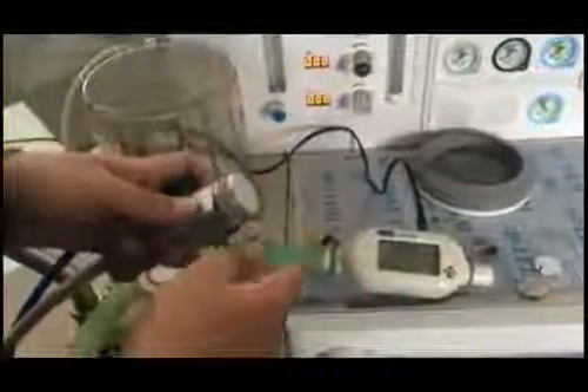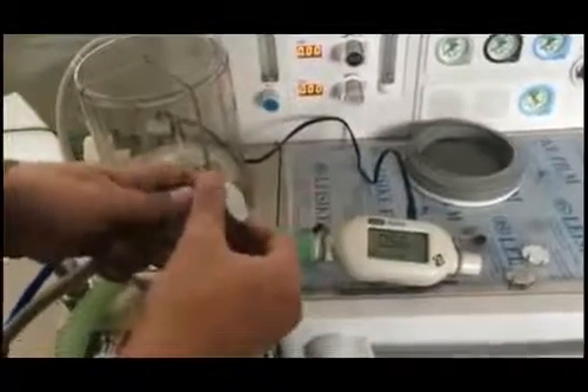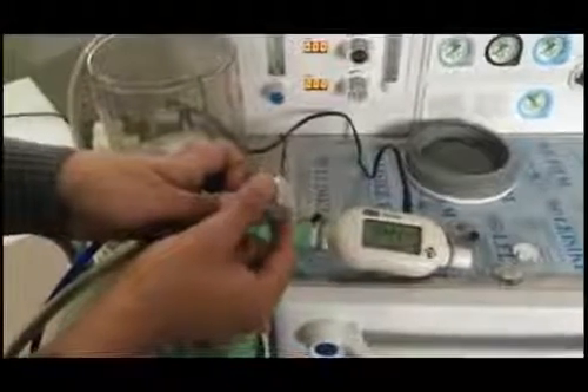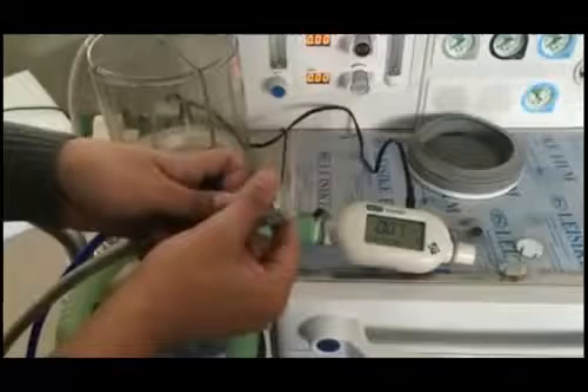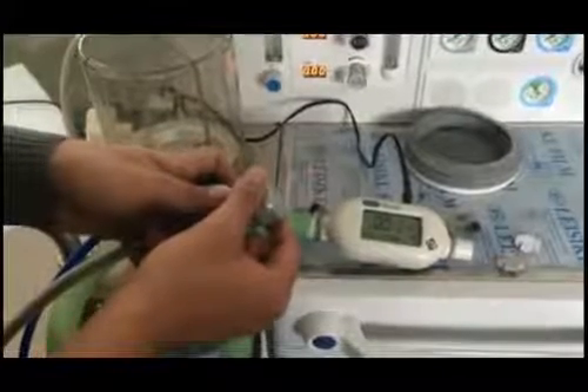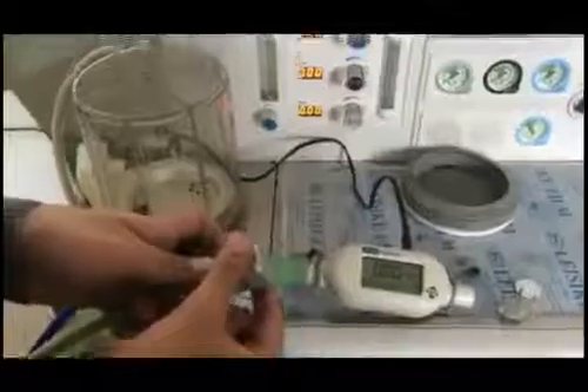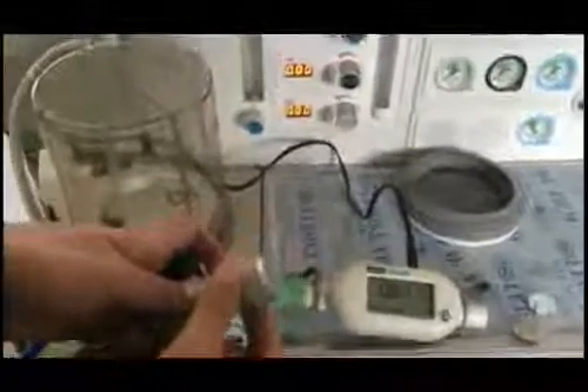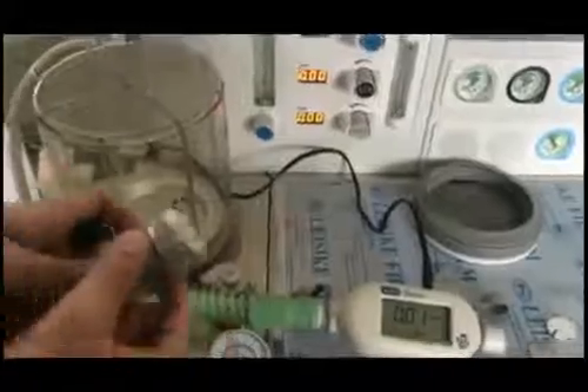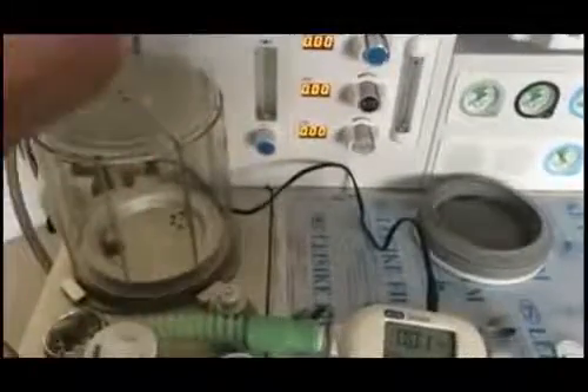Before pressing the 0 key on the screen, please look at the flow meter. Right now the flow meter is displaying 0.57. Please rotate the throttle to decrease the flow until 0 is reached. As you can see on the flow meter, the 0 has been reached. Wait for a few moments and then press the 0 on the screen. When you press the 0 on the screen, a calibration will be performed. If the calibration is successful, a green sign will be displayed.